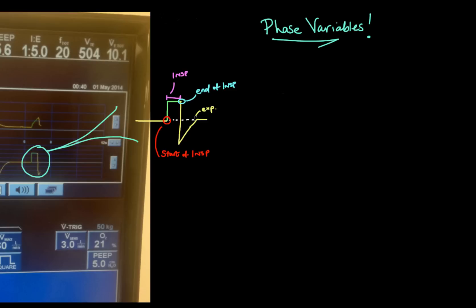What is a phase variable? A phase variable is something which happens within a breath type. You can see here that we have a couple of phases of a breath and some key milestones. From the ventilator screen shown in the last video, inspiration is this green square box and then it goes to expiration when it goes yellow down and then back up to minimum flow. The first key milestone is what causes us to go from expiration into inspiration — what tells the ventilator that we want to go from expiration to inspiration. We call this the start of inspiration.